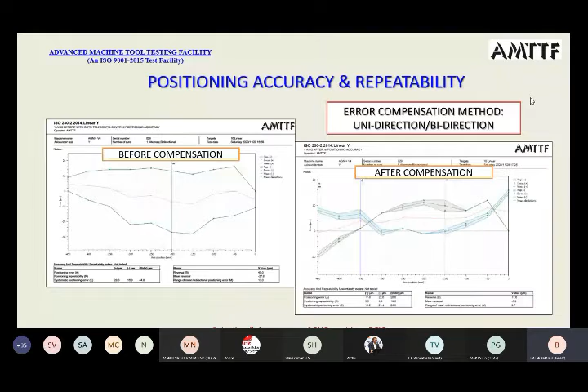Next, the vibration levels. Why I am telling you: I have a lot of queries regarding this particular vibration level from my users. They say I want 1 millimeter per second, I want 1.5 millimeter per second, I want 1.15 millimeter per second. It's again a notion. It depends on what you look at. Nobody has any idea what the effect of this is on your component accuracies. But there is a standard, 17243, which came out about 3 years back from ISO. We are trying to adapt the same standard to BIS standards, maybe in the coming few months.